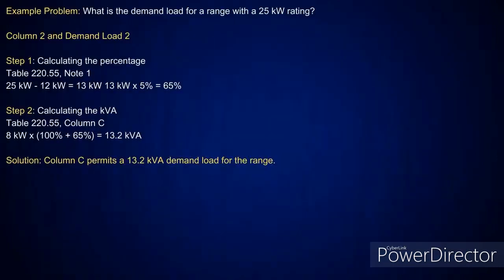All right, and I want to point one other thing out. When we start doing our full calculations, you're going to see we put everything in VA. The reason we put it in VA is because when you divide by the voltage, that gives you your amperage. Now, let's look here. I've got a 25 kW rating here. All right?